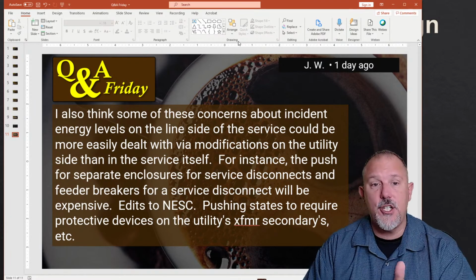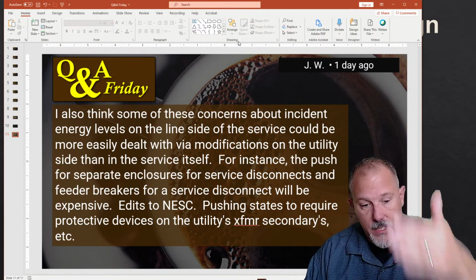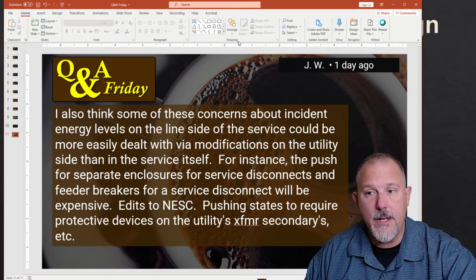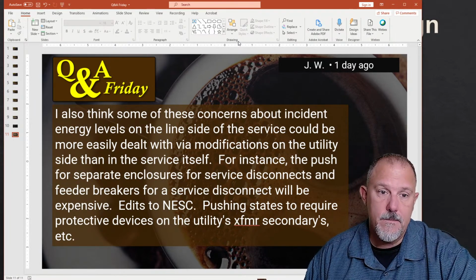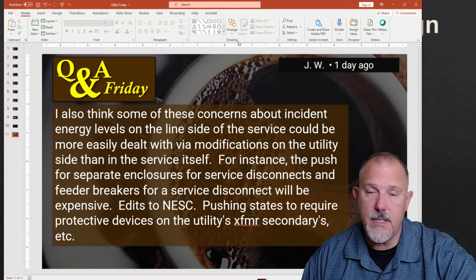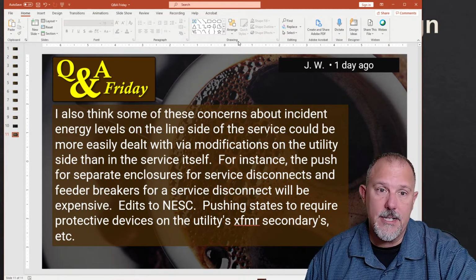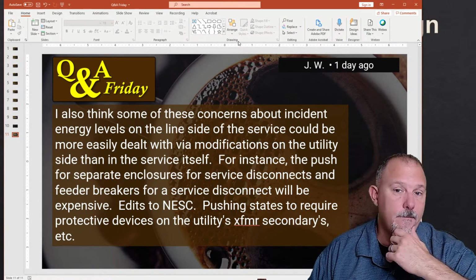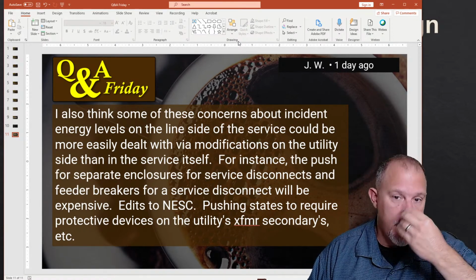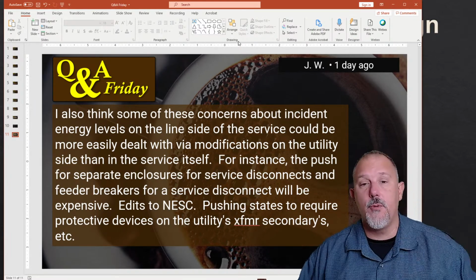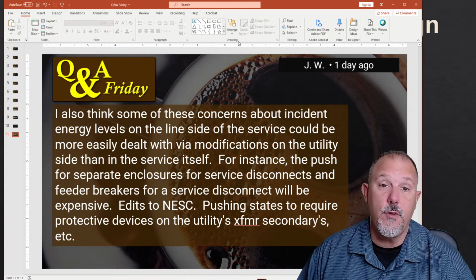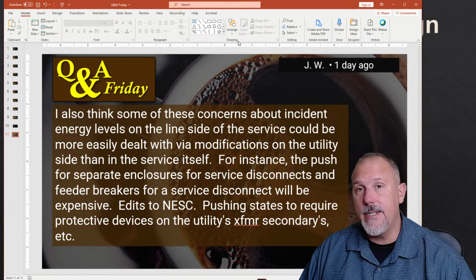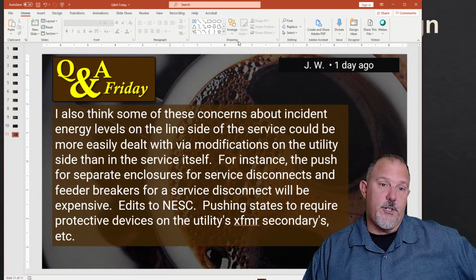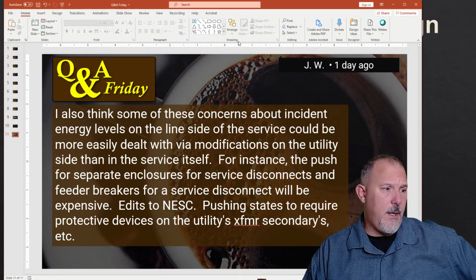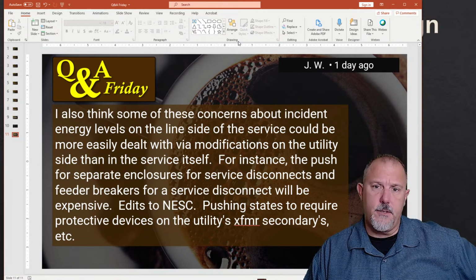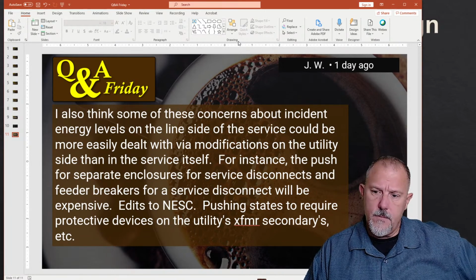So NESC needs to step up to the plate. I think some of the utilities, when they put equipment out there, they need to facilitate that. Help those facilities establish an electrically safe work condition and help reduce the incident energy. And I don't necessarily disagree with pushing states for requirements for the utility to provide secondary arc reduction technologies. That's I think a noble, valid discussion, JW. Absolutely. All right.